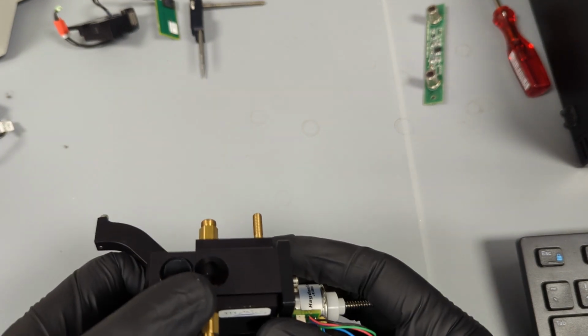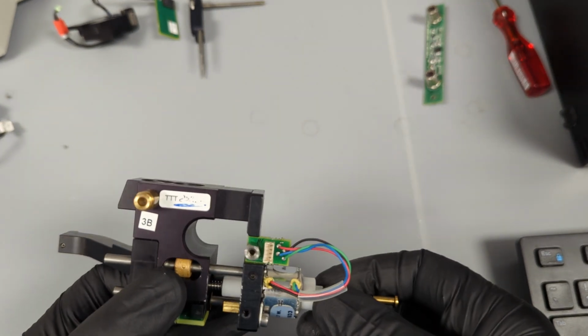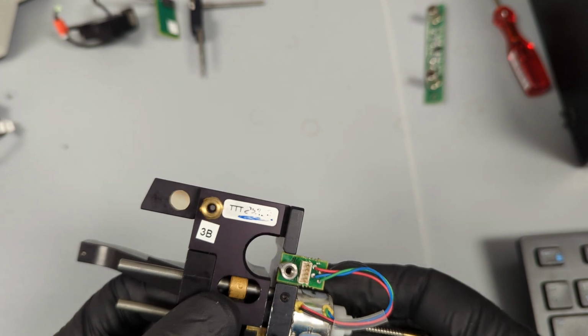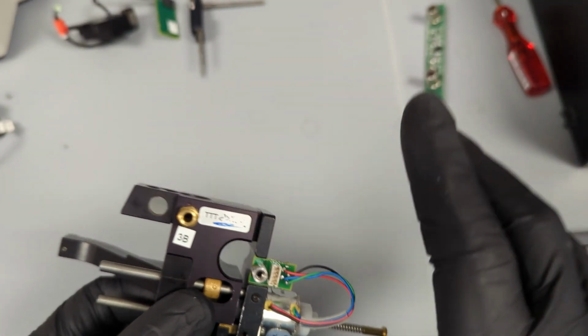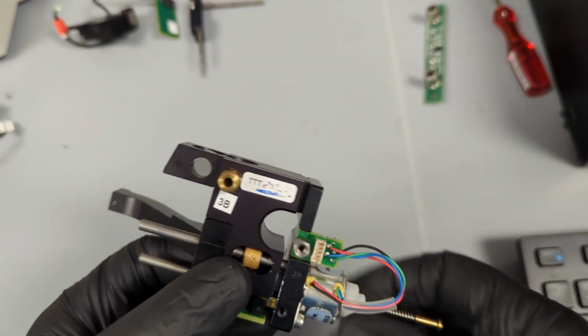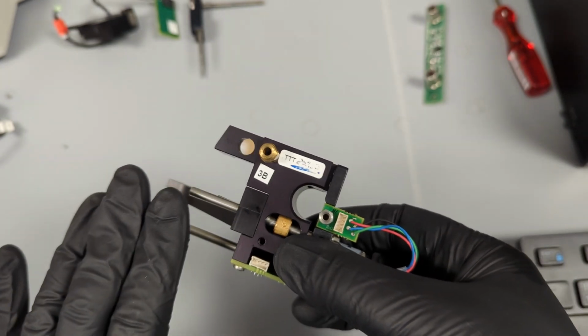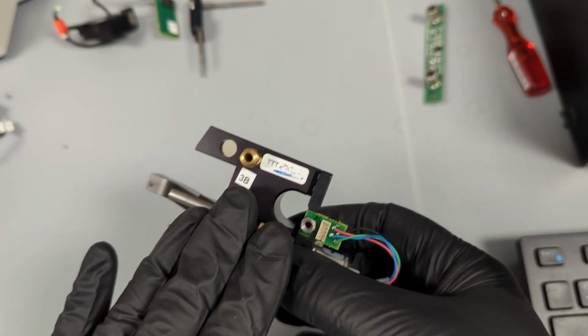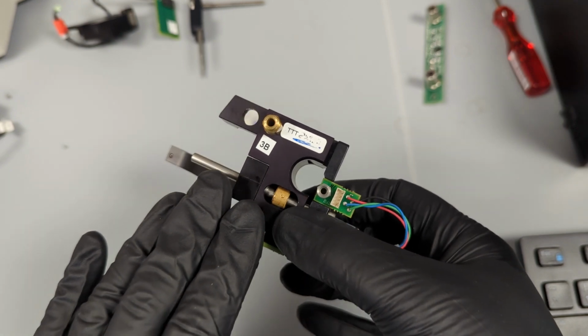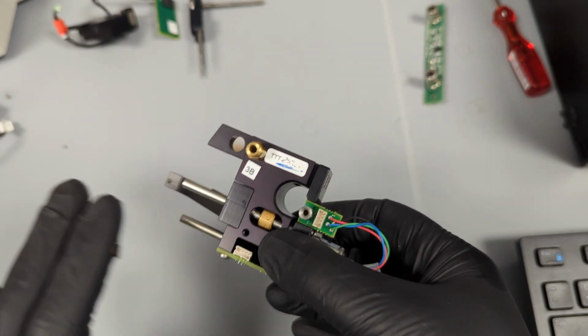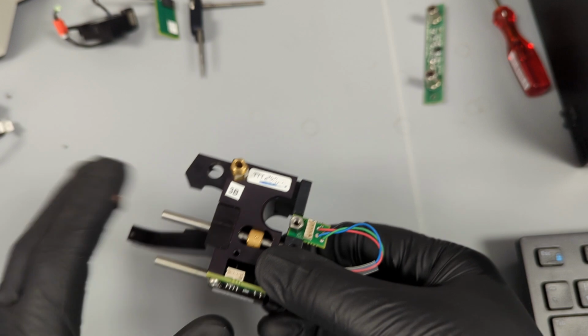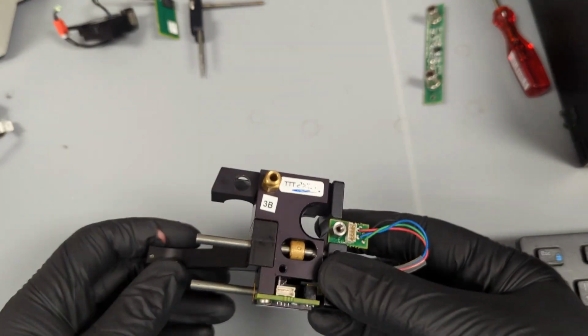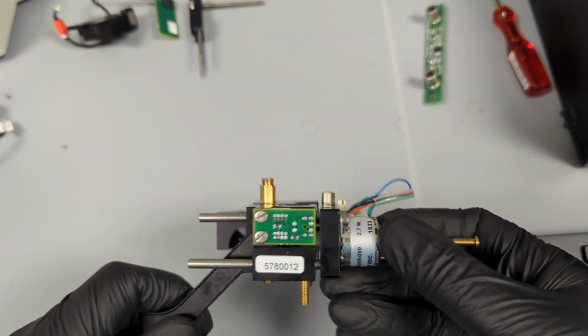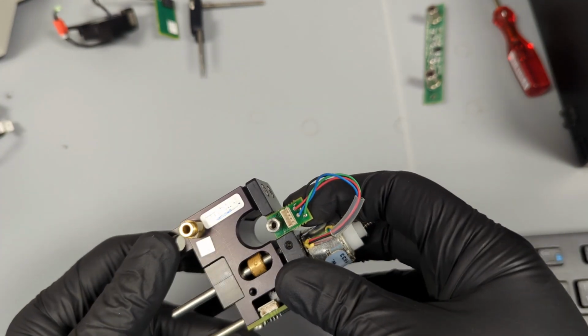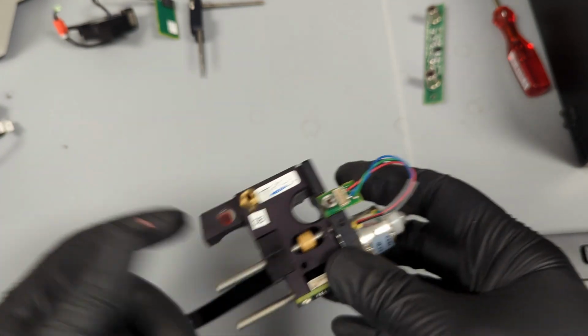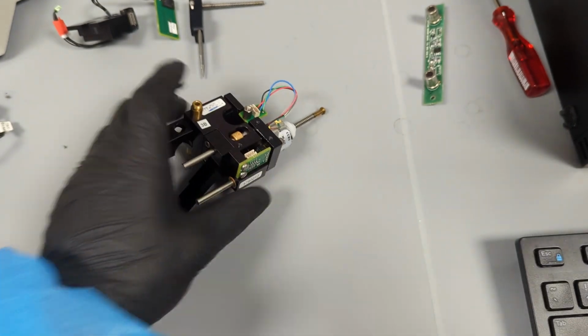All right, so that is what this guy is doing. These things are really finicky. I would not mess with these at all. Do not try to pry them if they're causing errors and they're getting stuck. Do not touch these. Best is to control them through the service mode if you're having any issues or you need to reset it, but do not manually try to reset them. They are a real pain, and this is a part that PerkinElmer will not sell to you directly, so this will require a service visit if it goes bad. But just thought I'd share that with you.